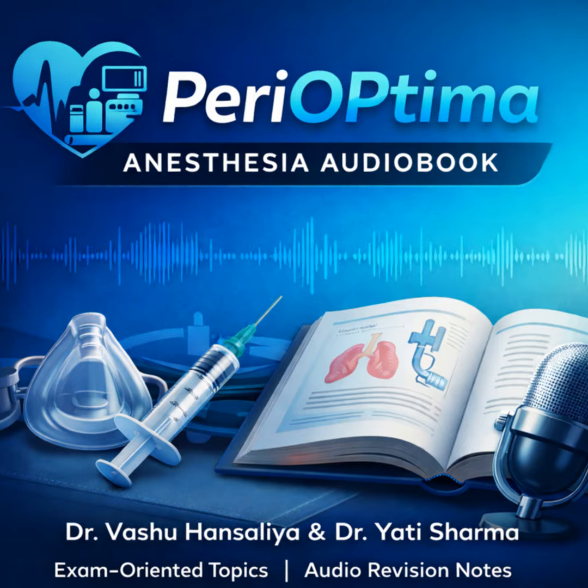And the Mapleson F, the Jackson-Rees modification. The arrangement is a Mapleson E with a crucial addition. A reservoir bag with a small escape hole, or a little APL valve at its tail. So it keeps the low resistance but adds control. Exactly. It retains the low resistance of the E, but the bag allows the anesthetist to assist or control ventilation, which is absolutely vital for neonates and infants. So E and F are preferred for pediatric anesthesia, especially in neonates and infants and also in MRI, and really any time resistance must be absolutely minimal.